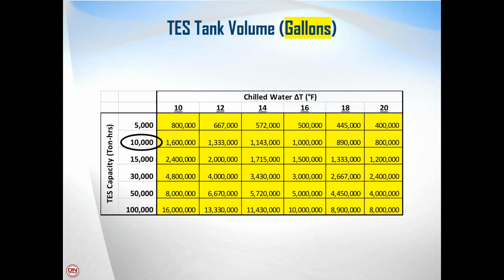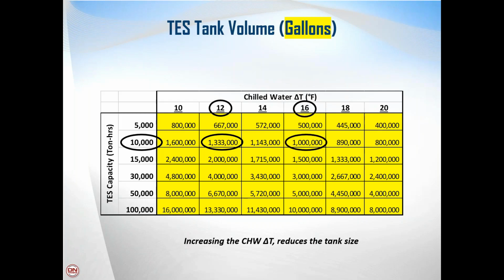So as an example, if an owner needed 10,000 ton hours of storage capacity in that tank, and they had a 12-degree differential between their supply and return water temperatures, they would need about a 1.3 million gallon tank. But if they had a 16-degree delta T in their chill water, still needing the 10,000 ton hours, now they only needed a 1 million gallon thermal storage tank. So they needed a smaller tank.